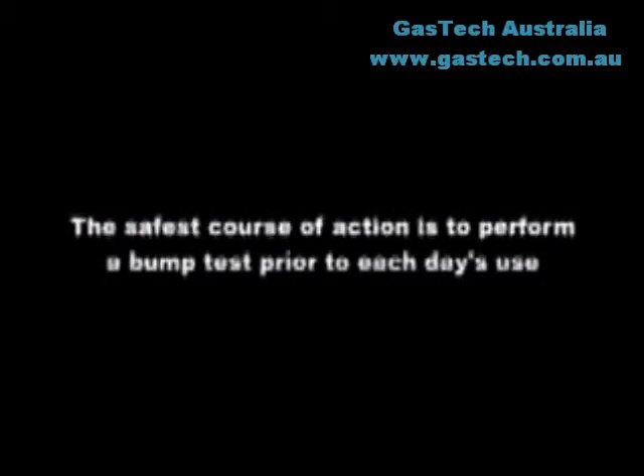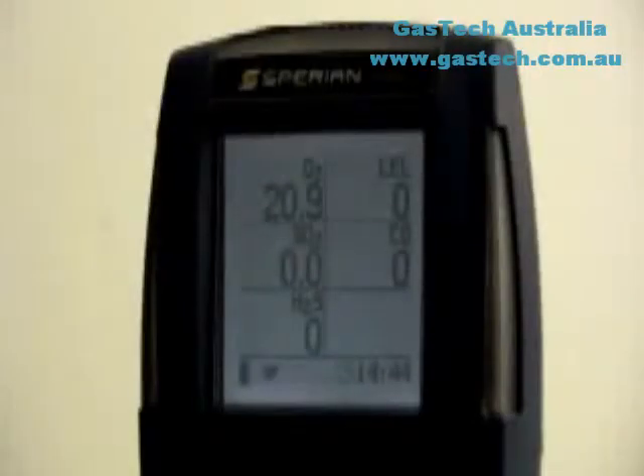Exposing the instrument to a known concentration of test gas will show whether the sensors respond accurately and whether the instrument alarms function properly. The simplest way to test sensor response is by performing a bump test. Turn the PHD6 on and allow the readings to stabilize. 5 minutes is usually sufficient unless the sensor has just been replaced. See the PHD6 reference manual for further details on sensor stabilization periods.